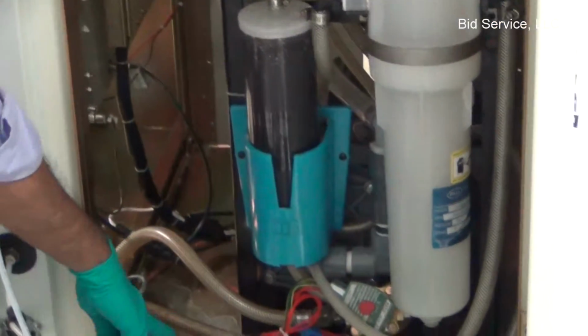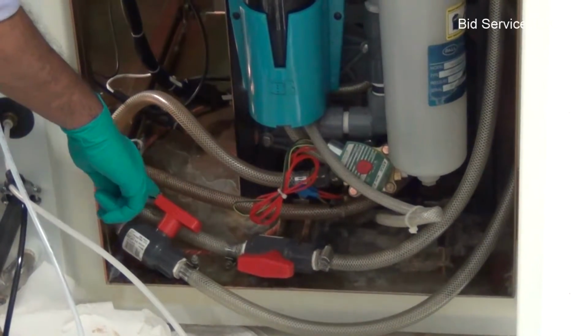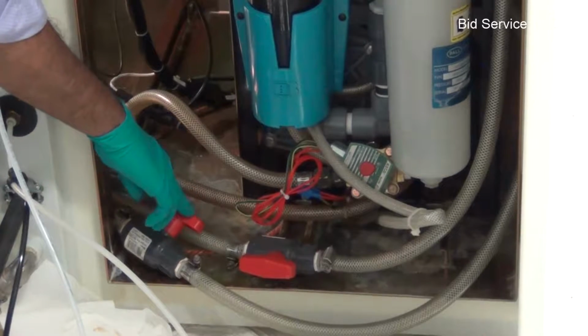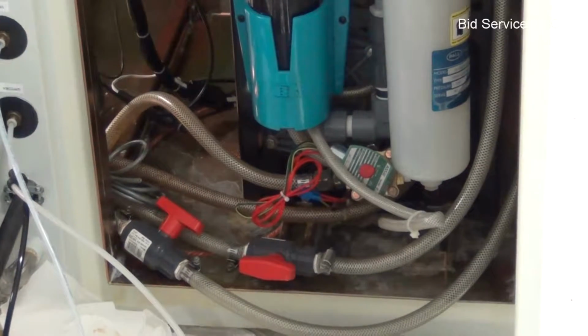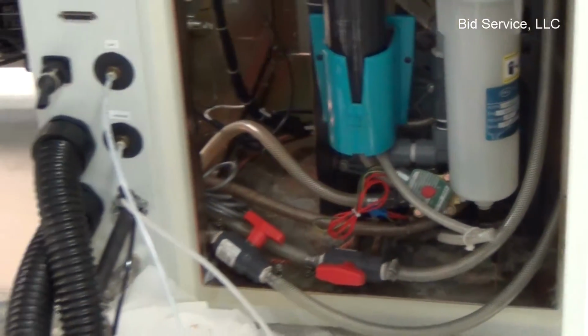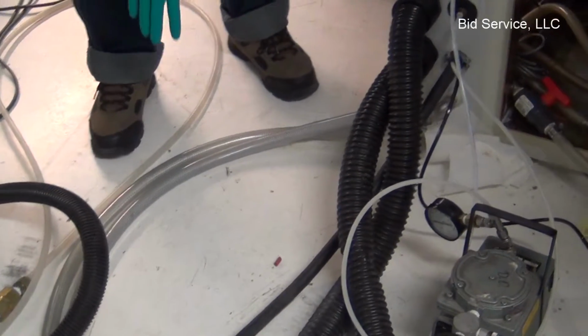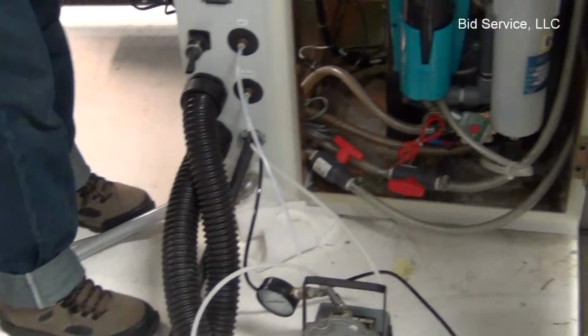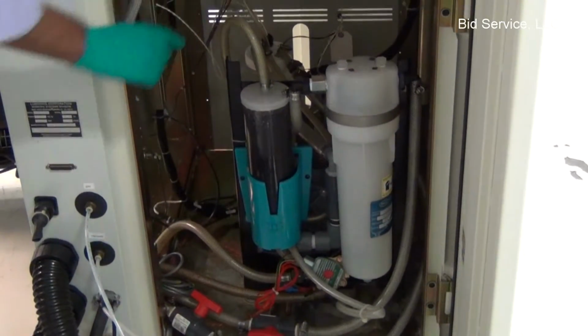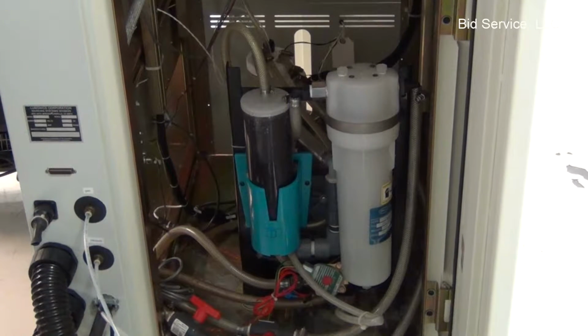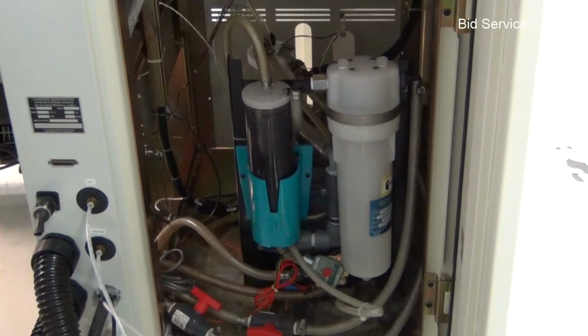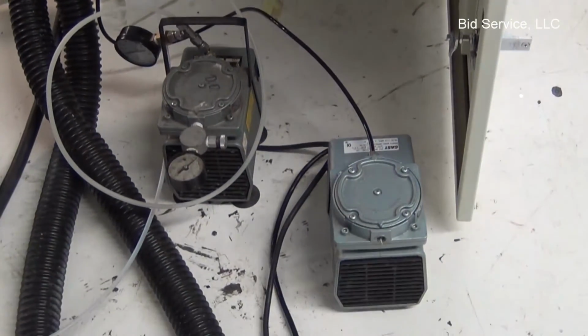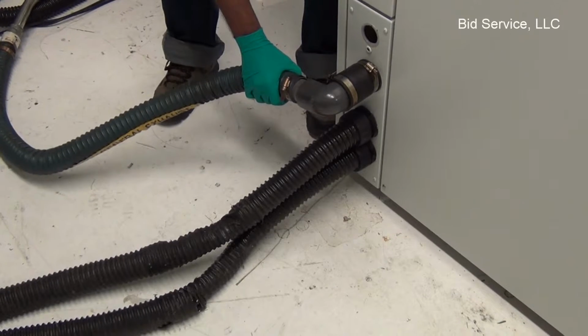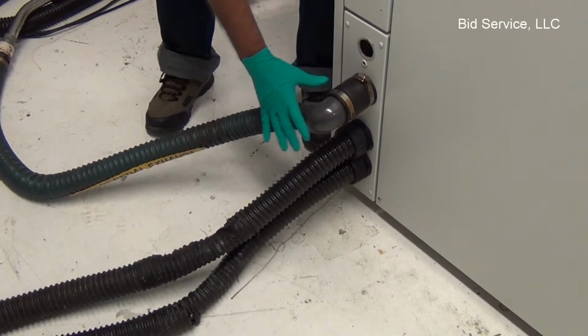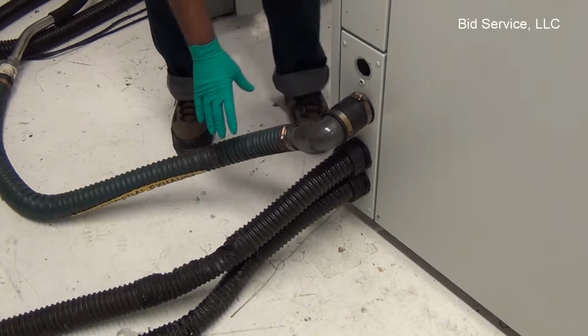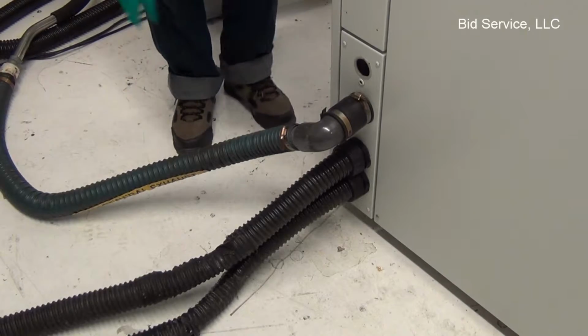And the system will be shipped with these two chiller water inline valves turned off, and the system requires either tap water or a recirculation chiller in order to cool the circulating DI water in the heat exchanger. This system does not include the chiller or the vacuum pumps. This is the exhaust line connected to the process chamber, and which needs to be connected to a vacuum pump or for dust collection from the process chamber.